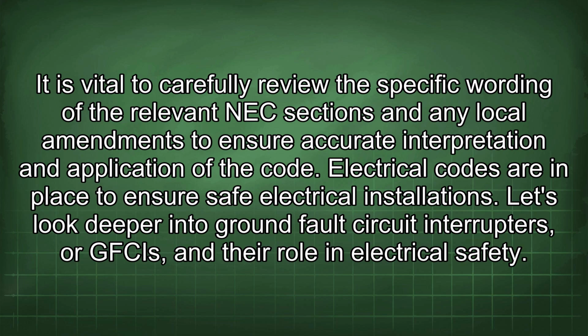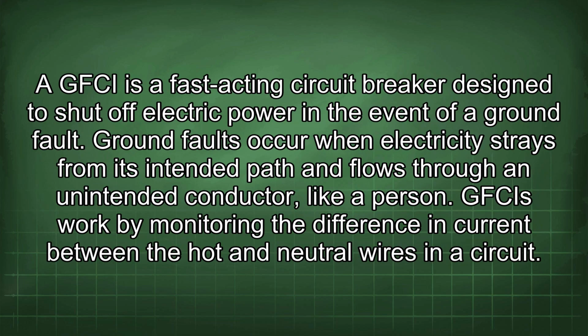Let's look deeper into ground fault circuit interrupters, or GFCIs, and their role in electrical safety. A GFCI is a fast-acting circuit breaker designed to shut off electric power in the event of a ground fault. Ground faults occur when electricity strays from its intended path and flows through an unintended conductor, like a person. GFCIs work by monitoring the difference in current between the hot and neutral wires in a circuit.